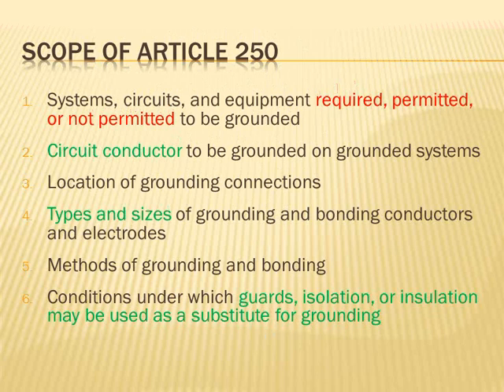Yes. Here's the option: double insulated equipment, like a drill. Some drills don't have a ground. You have two prongs, not a third one on the ground, because they're double insulated. Highly unlikely that the frame will be energized and you grab it. If you isolate the system, guard the system, you put them in an area, utilities use this one, and you don't ground the frame of them because they're isolated. Only qualified people can get in there, so you don't want to ground the frame because it interferes with the operation of the equipment.